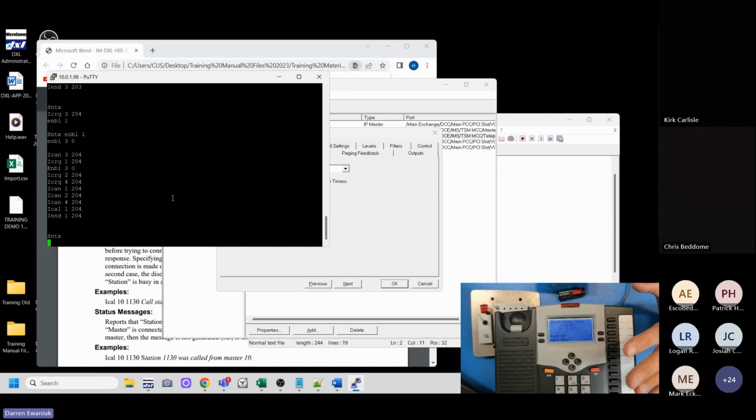So if I want master 3, which is my living unit master, to temporarily forward only to master 4 when this unit is unstaffed, you can use the set secondary command, or set S. What that does is, when that master is disabled, its secondary is redirected to something other than what you have in the configuration.